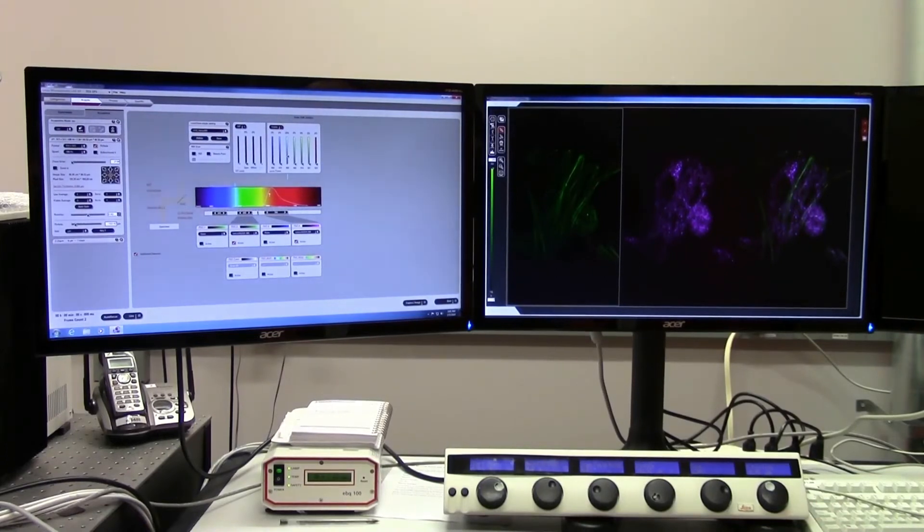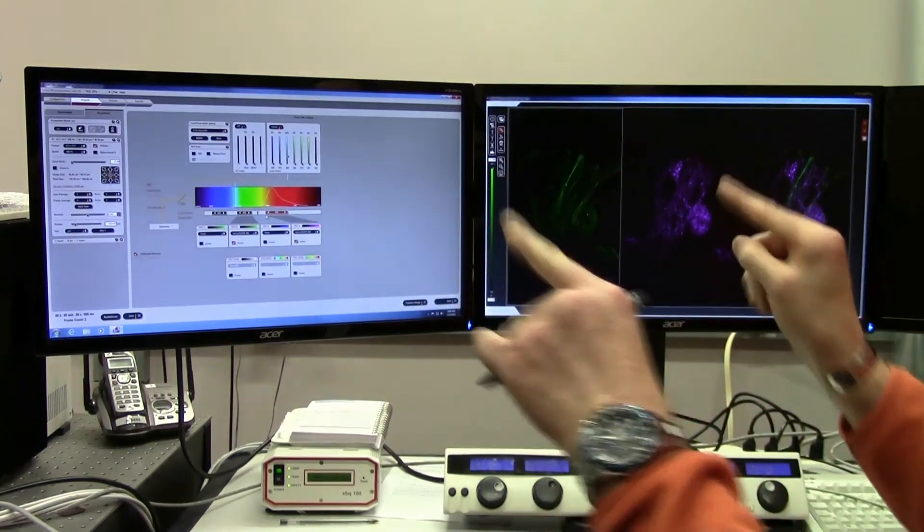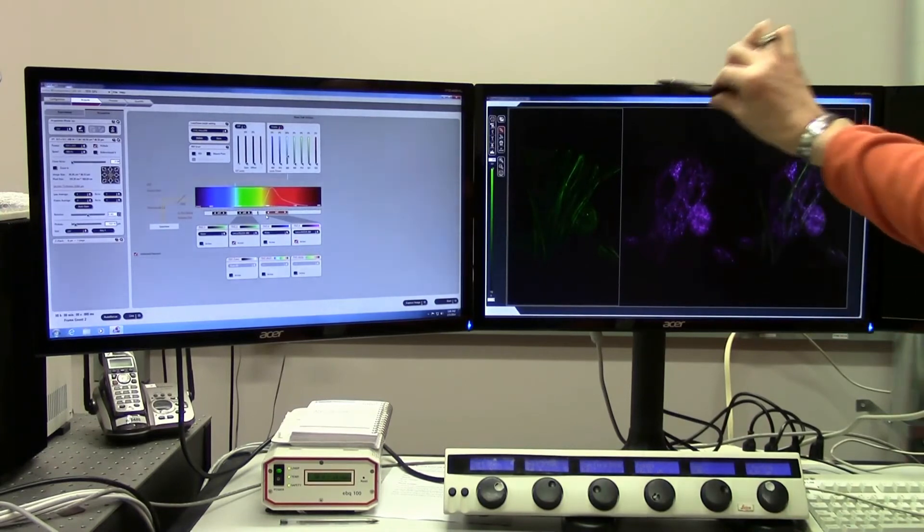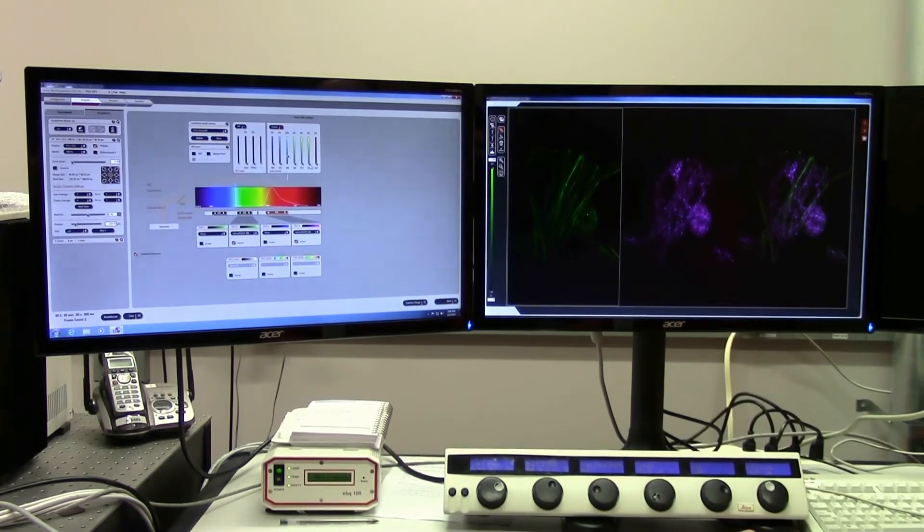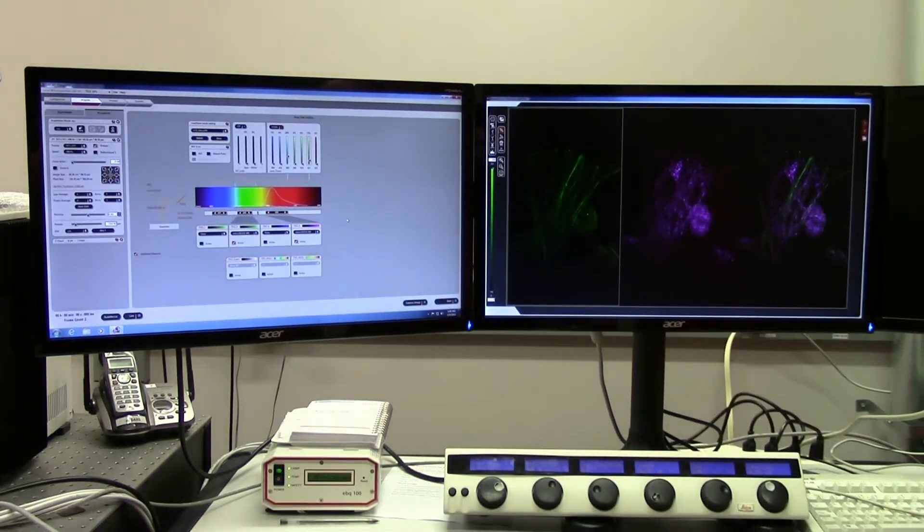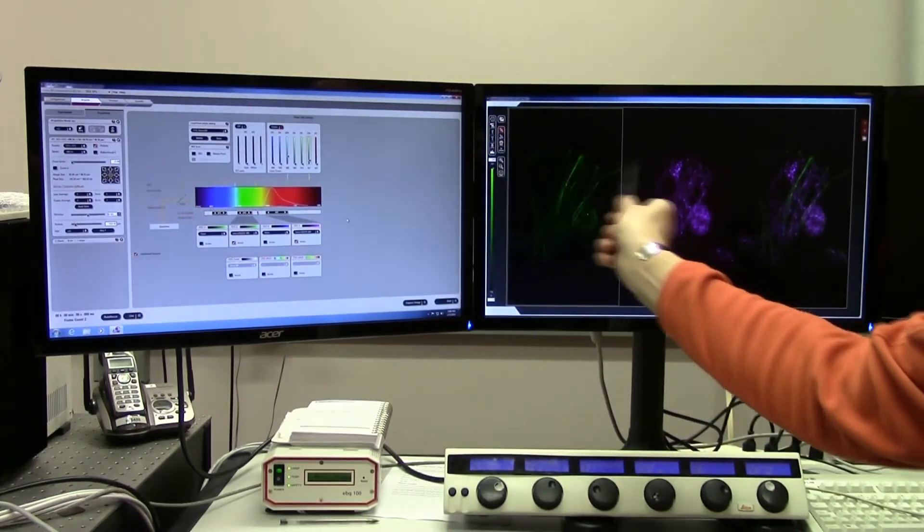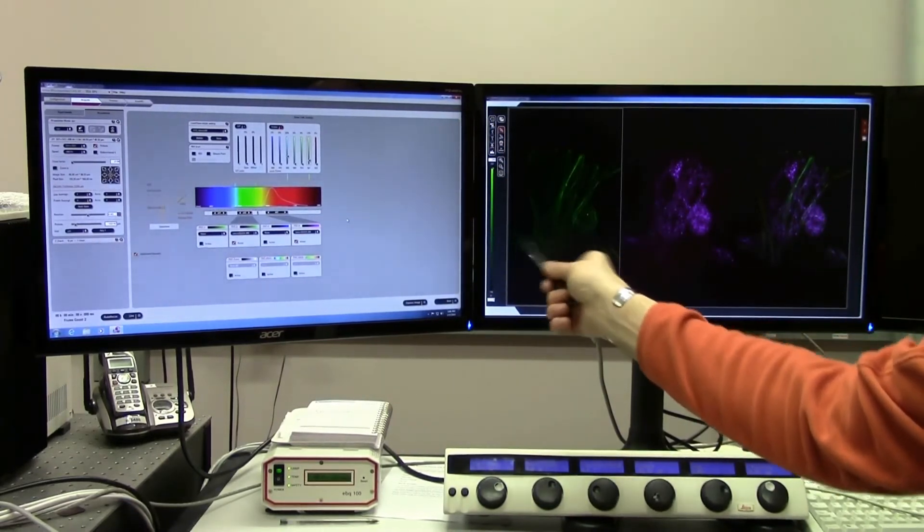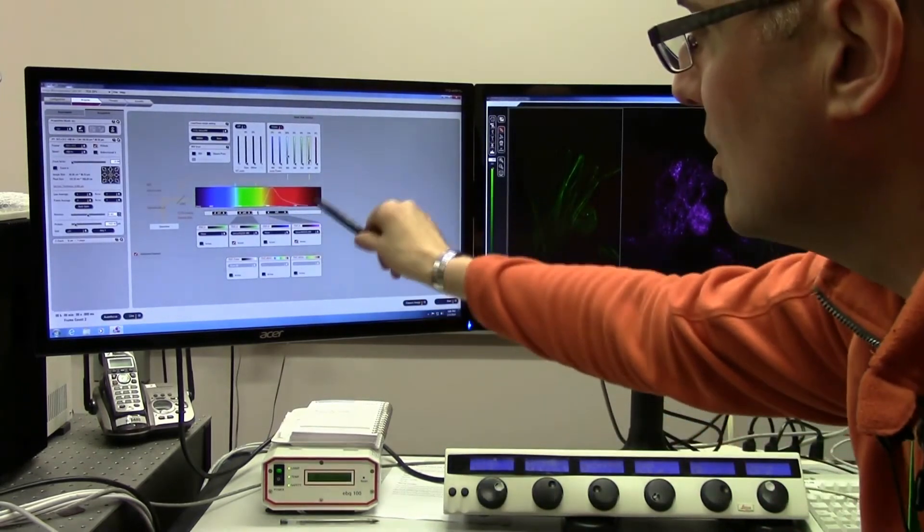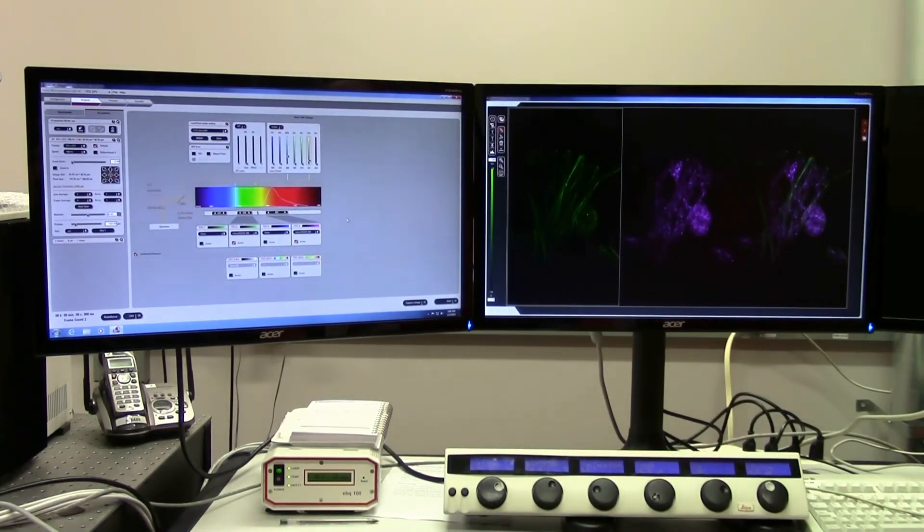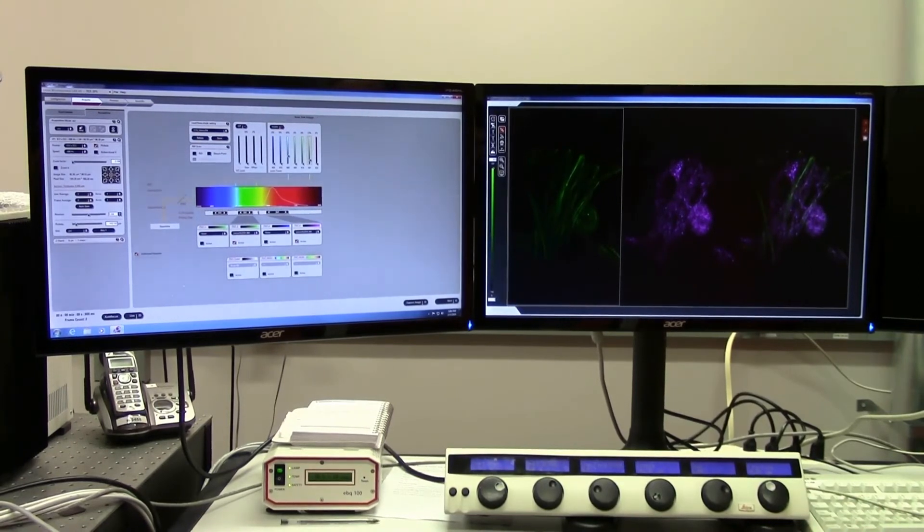If we did have any optical bleed between these two channels, we could adjust that by either increasing or decreasing the width of this profile. But as we did these scans, even with the two laser lines, you have to consider that when two laser lines are turned on, both lasers are scanning across the surface of this image, sending all that light over to the PMTs that is then gated for selecting your emission profile. The more accurate way to do this is with what's called a sequential scan.